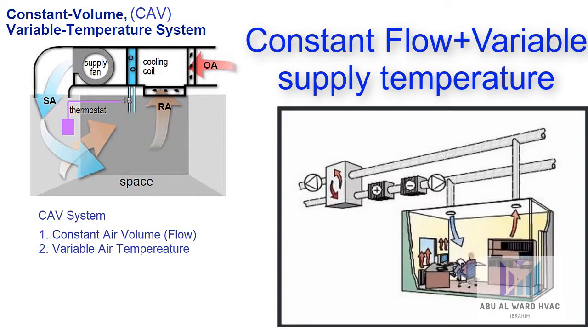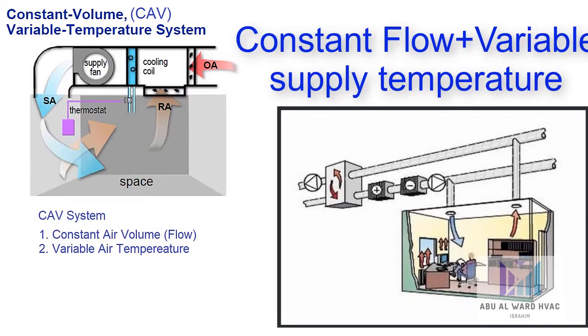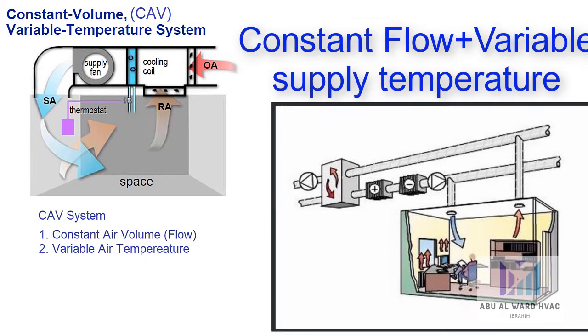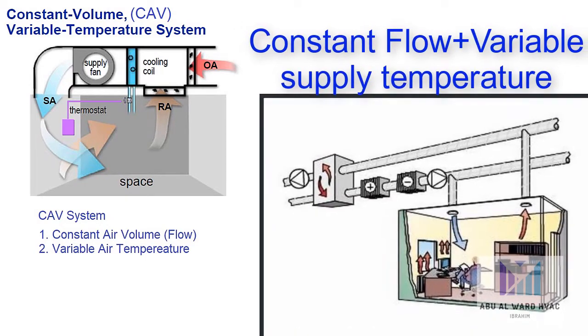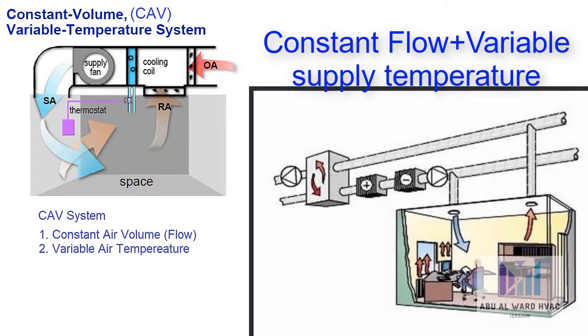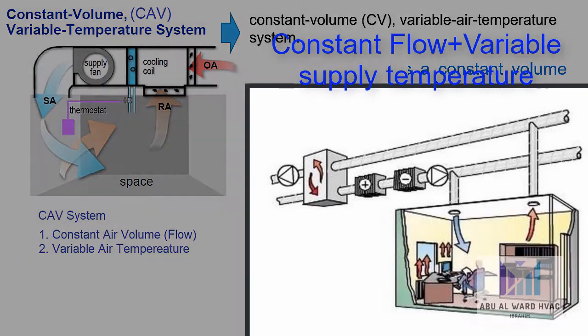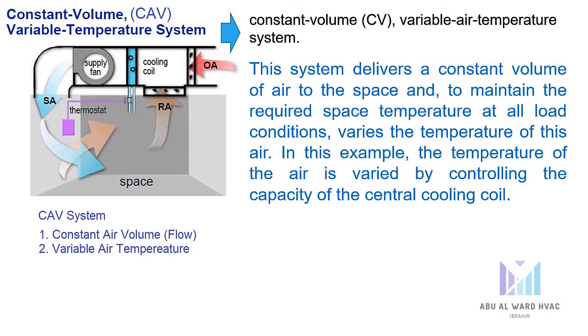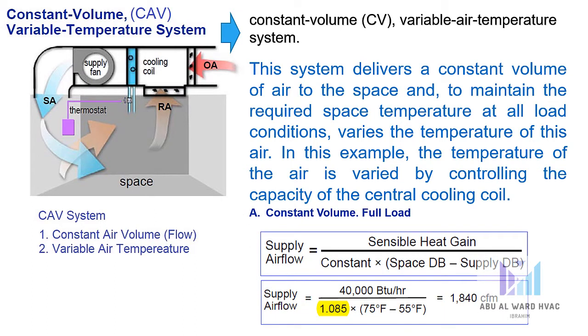When supplying air to the space, the temperature of the air will be varied while the CFM (air flow) will be constant. This system delivers a constant volume of air to the space and maintains the required space temperature at all load conditions by varying the temperature of the air. The temperature is varied by controlling the capacity of the central cooling coil.